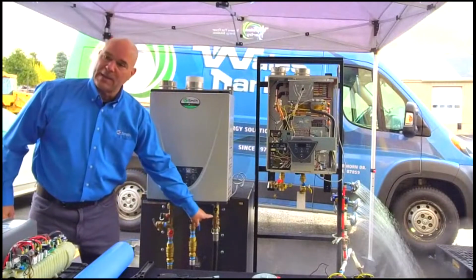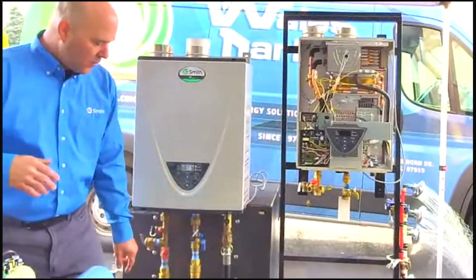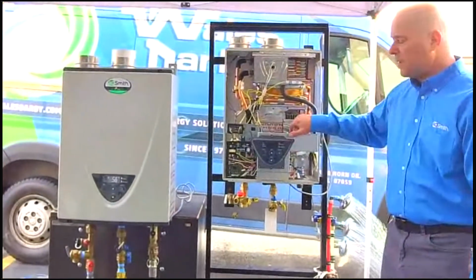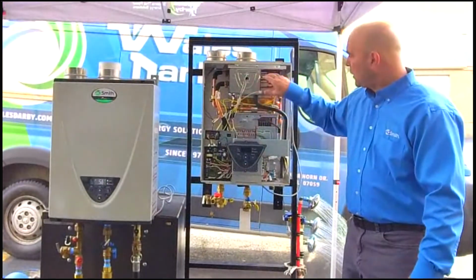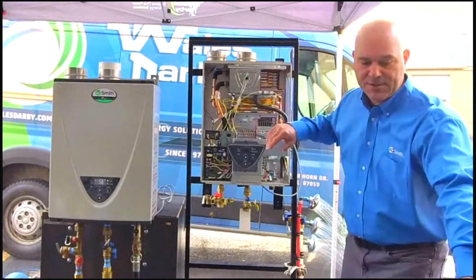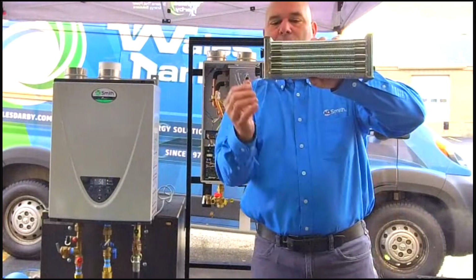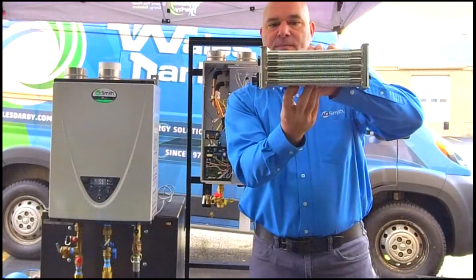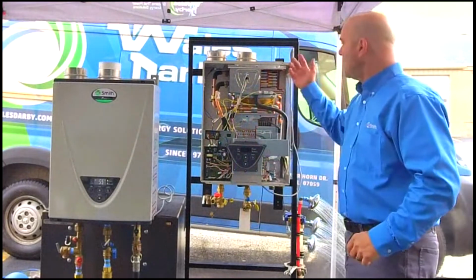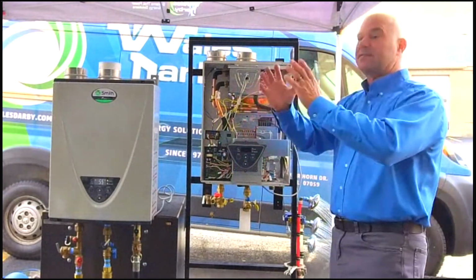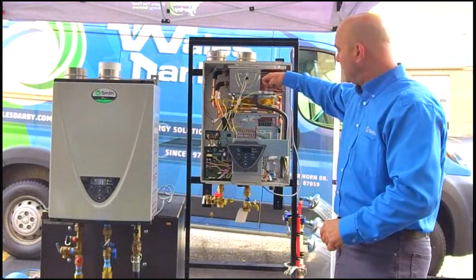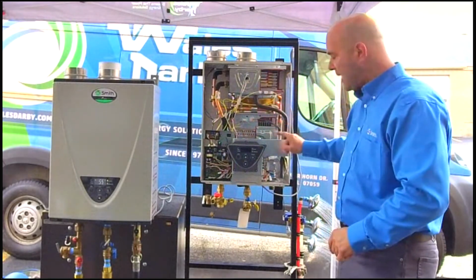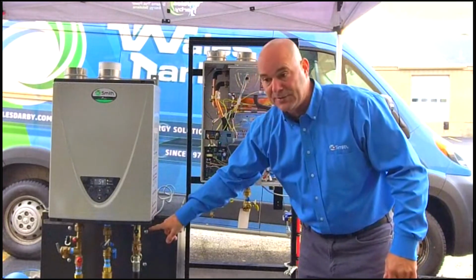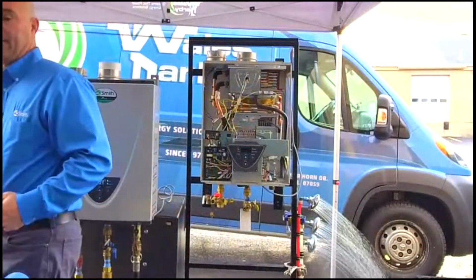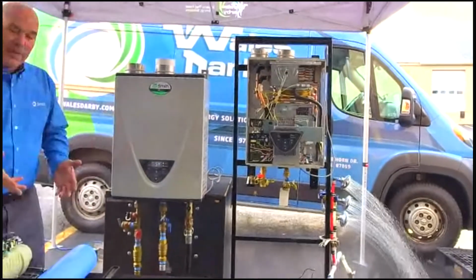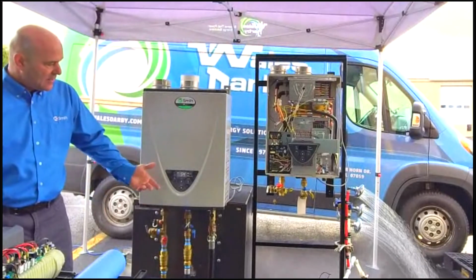This is good. See the water dripping out of the bottom right here? This is condensation. So what's happening right now is we have combustion taking place here. We're collapsing the flue gases in this secondary heat exchanger. So our water's going through here, our flue gases are running across this, and as that's running across there, we're collapsing the flue gases. We're taking that gas, turning it back to a liquid. That's running into our collection tube, down through our condensate trap, and is dripping out of the bottom of the unit right now because we're making hot water. And this unit is condensing. And that's why we can get to those 95% efficiency rates, because we're condensing.